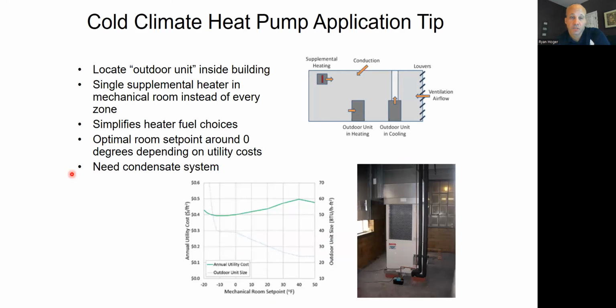If you're doing it in a cold climate, there are some things you can do slightly different. As you might guess, I'm going to have some kind of supplemental heat or size my heat pump so ginormous to cover the heat that it's grossly, grossly oversized for cooling in a lot of buildings. I don't usually want to do that. I might, if the building's really tight, built really well, sustainable style building with great windows and air tightness, and I got my heating and cooling loads pretty equalish to each other, right? Then I might be able to just go ahead and do it all with VRF or all with the heat pump in general, right? But if I don't have that, especially on retrofits, my heating BTU needs are more than my cooling.